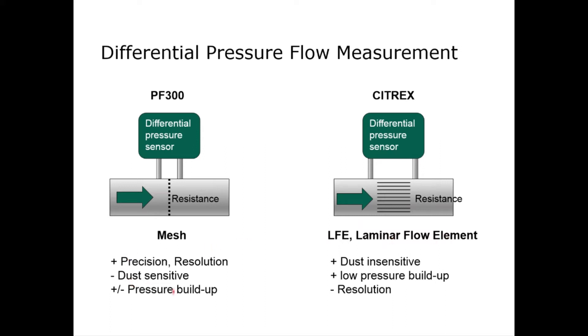When we look at the advantages and disadvantages: the PF300 has very high precision and resolution but it is a little bit dust sensitive. The pressure building up by the flow is a little higher which means it does affect a little bit the measuring chain. On the other hand, Citrex with the laminar flow element is completely insensitive to dust. The pressure buildup is very low but the resolution is a little less, particularly for lower flows.